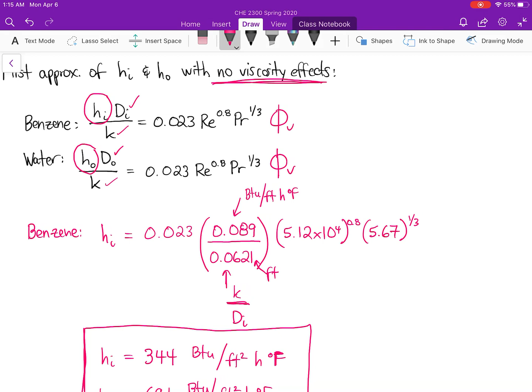I can then use that viscosity correction factor. I can come back up here and put my viscosity correction factor onto my Dittus-Boelter equation, making it the Sieder-Tate equation. From that, I can calculate what we'll call an updated hi and ho. So using that viscosity correction factor, we get an hi of 333. That's why that number was in my head earlier. BTUs per square foot, hour, degrees Fahrenheit, and ho equal to 703 BTUs per square foot, hour, degrees Fahrenheit.